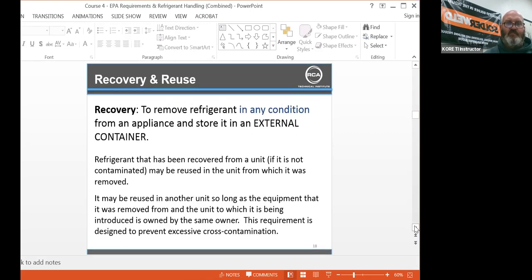Recovery: to remove refrigerant in any condition from an appliance and store it in an external container. Refrigerant that has been recovered from a unit, if it is not contaminated, may be reused in the unit from which it was removed. It also may be reused in another unit so long as the unit to which it is being introduced belongs to the same owner. This requirement is designed to prevent excess cross-contamination.